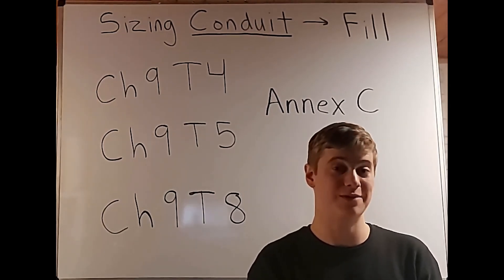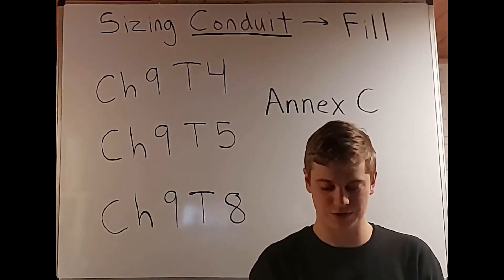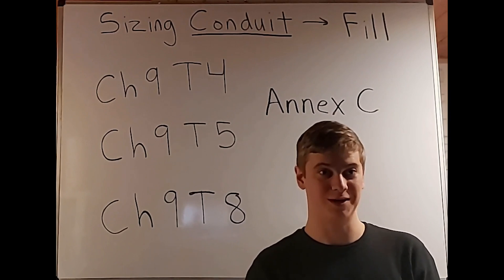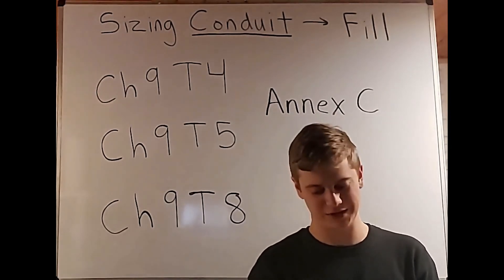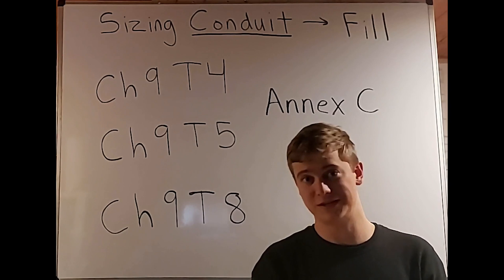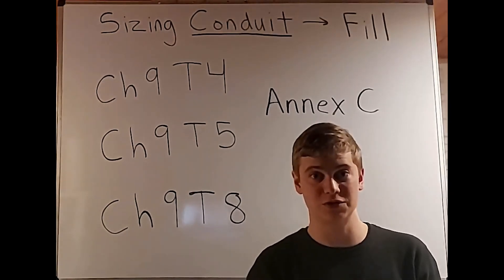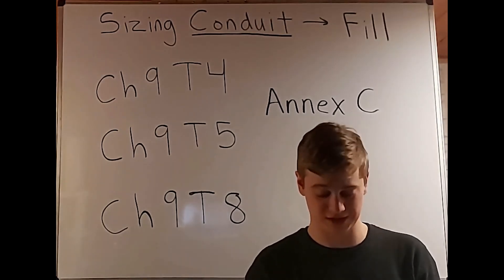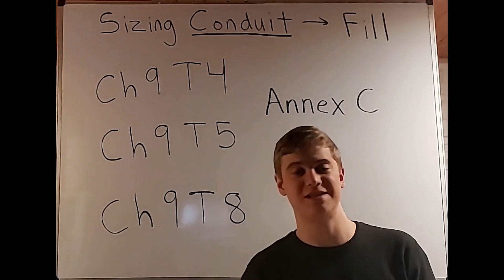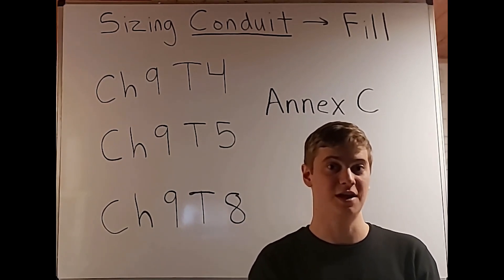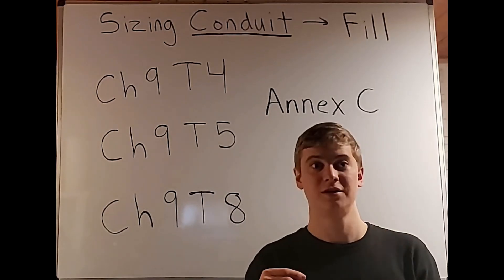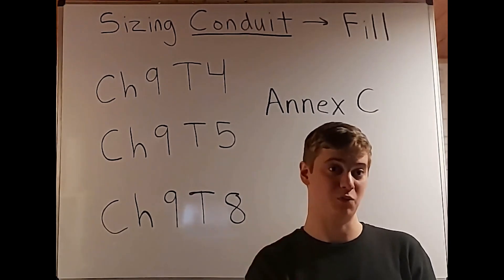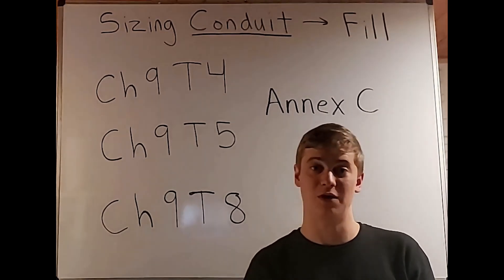Here's where things get a little interesting. If we have two cables, we're at 31%. But then if we have over two — meaning three or more — you're going to have the demand factor of 40%. Luckily, this is most of the time already in the tables we're going to be using. All you have to do is look at the 40% column if you have over two wires, or the other two columns that fit what you're working with.